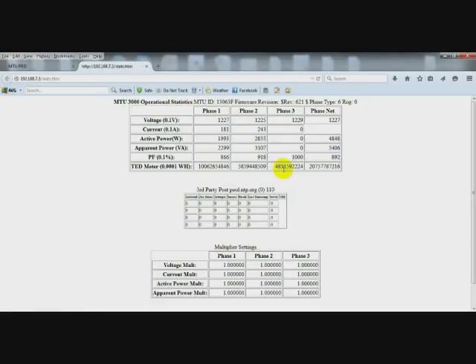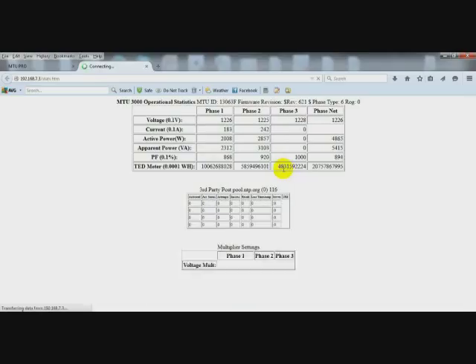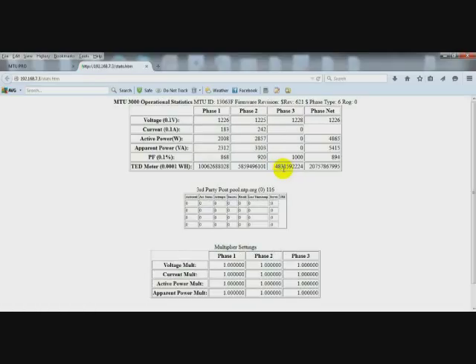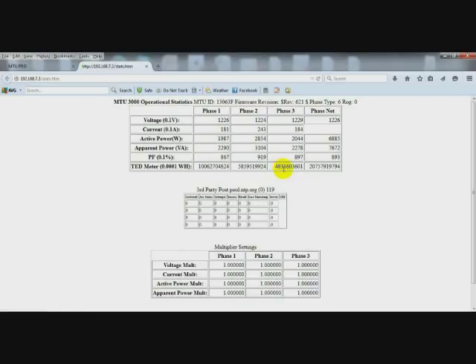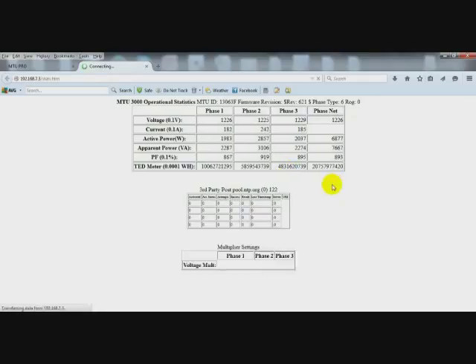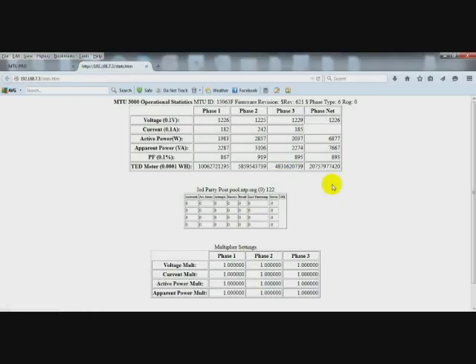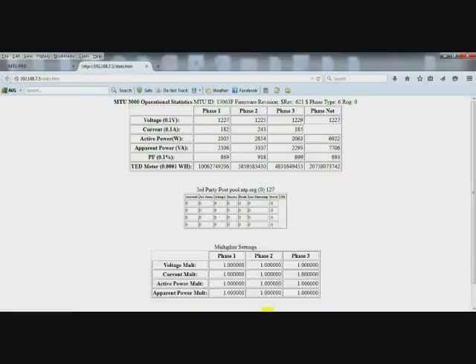And we know the next connection is going to be phase C, which it is. And we have an active power positive for each phase. So we know that our CT connections are now matching our voltage connections for phase A, B, and C.